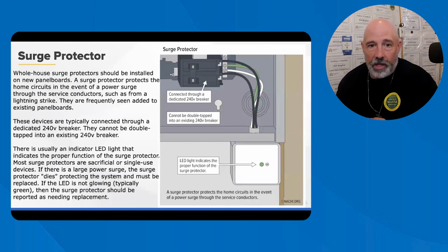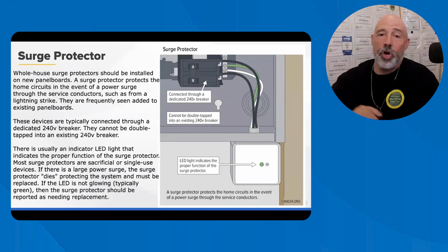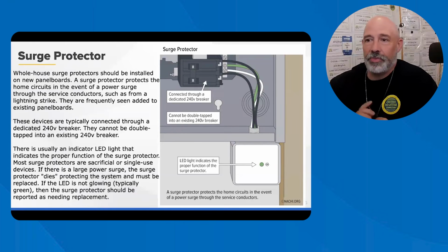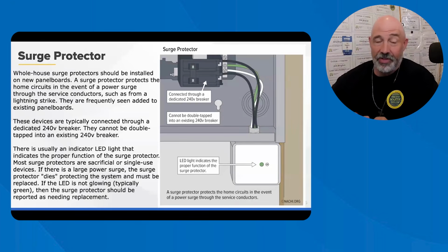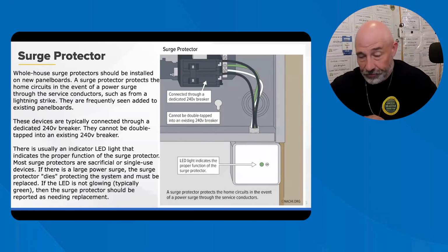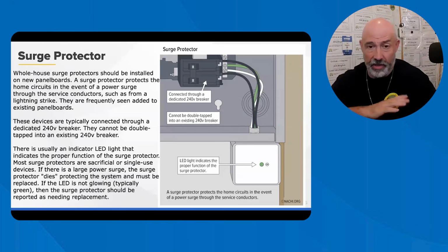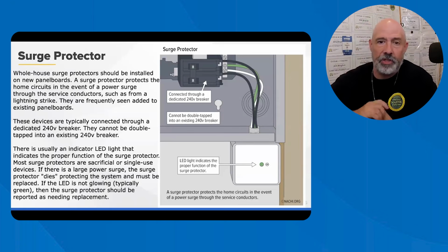So there you go. The 2023 NEC now requires surge protectors on new and replacement dwelling service equipment. Article 230.67 requires protection, while Article 242 covers the installation requirements for surge protection devices. You can read that if you do have a 2023 NEC. I always carry that with me. Most surge protectors are connected to a dedicated 240 volt breaker and should not be double tapped into existing breakers, just FYI.